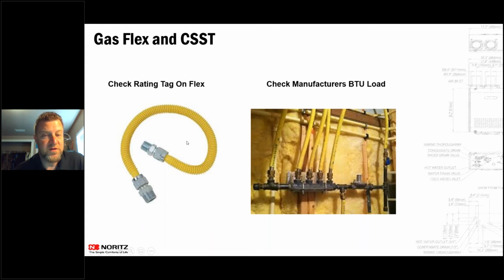Because we've seen a ton of installs where the main line coming in is just fine, but the gas flex is too small and it causes problems with the unit, because if we can't get to 199,000 BTUs when that unit is at full capacity, you will see error codes happening, and we've seen a ton of those gas flexes we tell people they need to change out because they put it in wrong. With CSST, I know it's become very, very popular in new construction and in retrofit applications. So this type of install where you have a 2-pound system coming in to the house, and then you're branching off everything to individual loads inside the house.